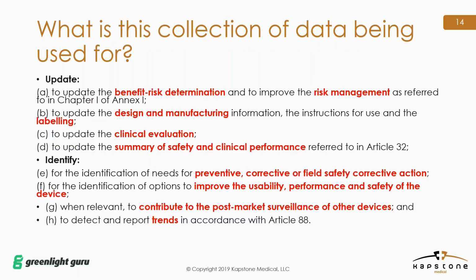So now that we know how to collect the data and where we're sourcing the data from, we need to get an understanding of, well, what are you going to do with that data? Article 83 actually gives you the expectations of what you need to do with this data. Data gathered by the manufacturer's post-market surveillance system will, in particular, be used for updating certain documents and identifying certain data points, and then we'll go into detail. So you're updating your benefit-risk determination. You're improving risk management, you're updating any design and manufacturing information, any labeling, the clinical evaluation, and then your summary of safety and clinical performance. You're also identifying any potential corrective or preventive action needs, any field safety corrective actions that need to be taken, and identifying any improvements to the device.